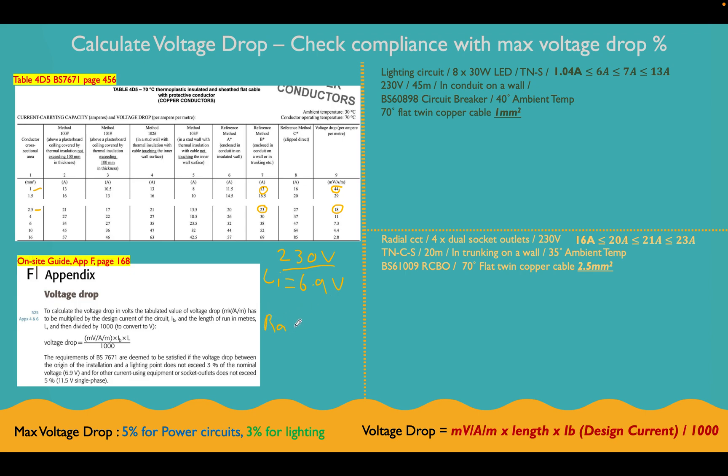And for our radial circuit, which is feeding the sockets, we can't exceed 5%, which is 11.5 volts. It's always good to write those down as voltages. It's just a little bit easier to actually see visually when you do these calculations. So we're going to calculate these, and it's going to give us a value in volts, and we're going to check that it's lower than these amounts.